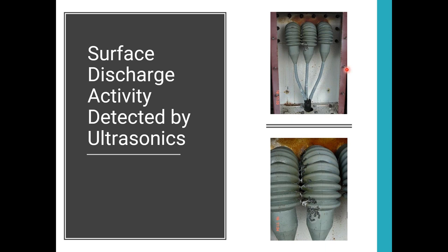Very similar to this cable up here. This one, we'll take a better look at. Stress cones, they didn't have the right voltage rating, so they put a larger stress cone on it. They went up a voltage rating. That shouldn't be a problem, but it's a non-shielded section of the cable, and it actually caused the stress cones to come in contact with each other. So it created a high electrical stress point at the contact points. If you look closely, you can see the white ash forming, the carbon treeing happening on the stress boots, going in both directions. There's a little more of an air gap between these two, so they've only got a little bit compared to these two phases.